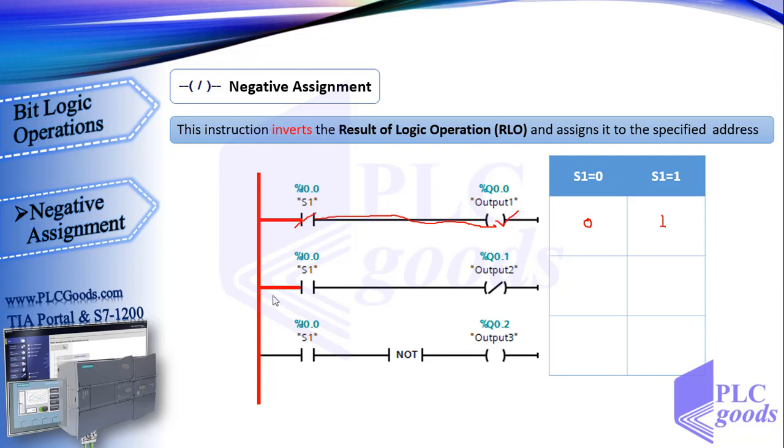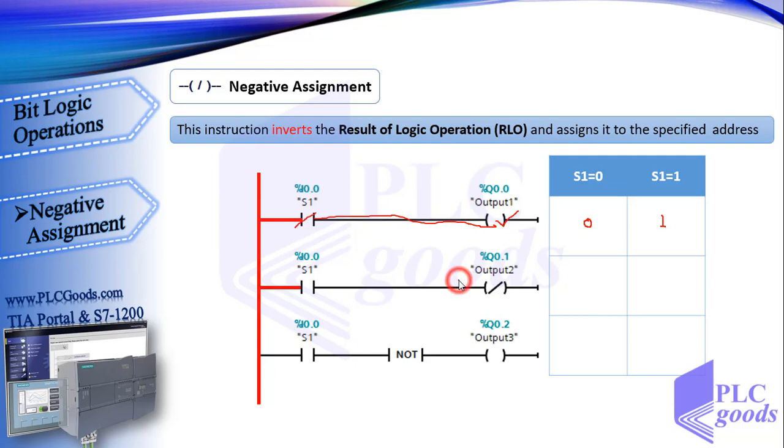Like the first line, in the second line, when S1 is inactive, the virtual power can't reach the second output. But here we've used a negative assignment instruction which inverts the RLO. Now here we don't have virtual power, so the RLO is 0. Then negative assignment instruction inverts it to 1, so this instruction makes output 2 be 1 or on.